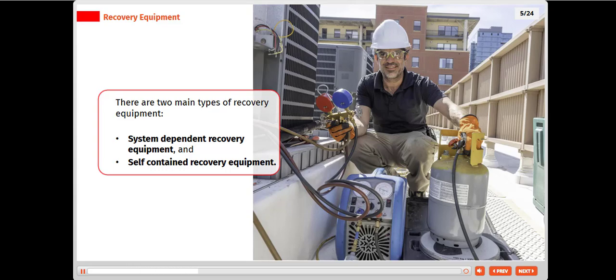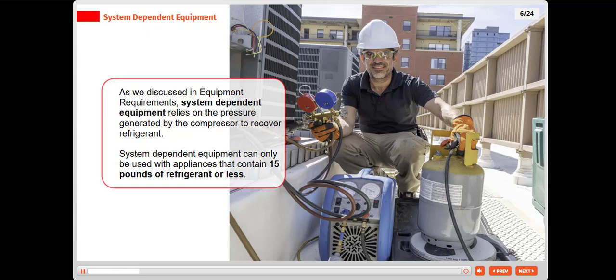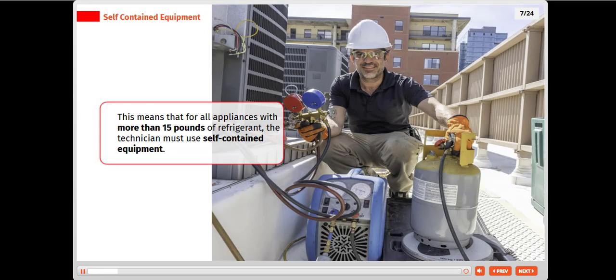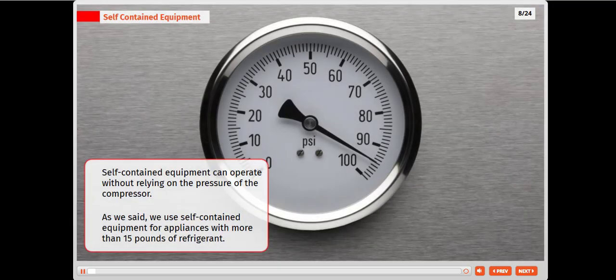There are two main types of recovery equipment: system-dependent recovery equipment and self-contained recovery equipment. As we discussed in equipment requirements, system-dependent equipment relies on the pressure generated by the compressor to recover refrigerant. System-dependent equipment can only be used with appliances that contain 15 pounds of refrigerant or less. This means that for all appliances with more than 15 pounds of refrigerant, the technician must use self-contained equipment. Self-contained equipment can operate without relying on the pressure of the compressor. As we said, we use self-contained equipment for appliances with more than 15 pounds of refrigerant.